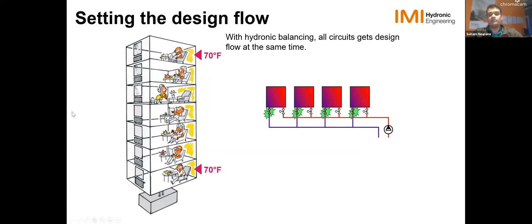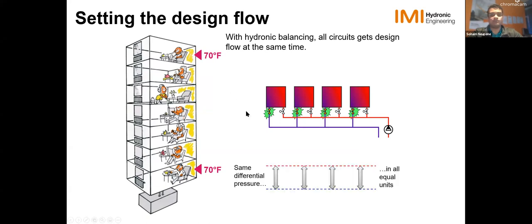And that way, what happens is the differential pressure distribution through all these units, assuming the same flow, is going to be more or less constant. So this differential pressure is going to be constant, and as a result, you'll not see overflow and underflow, and you'll see more even distribution of temperature throughout the building, which is exactly what we want. We want to avoid the gradients as much as possible. And thus we want to focus on balancing and make sure we have proper balancing solution installed in the buildings.